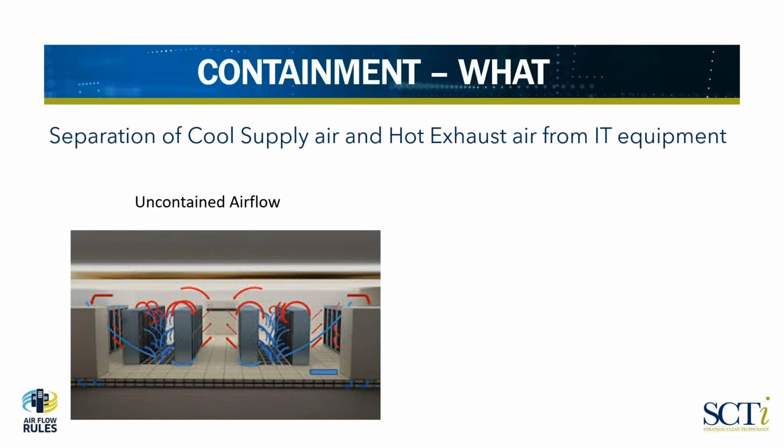On the what side, it's pretty basic. Containment essentially is the separation of cool supply air and hot exhaust air from the IT equipment. And as you can see in the diagram on the left, without containment, you have cool air coming up through your perforated tiles if you have a raised floor environment.